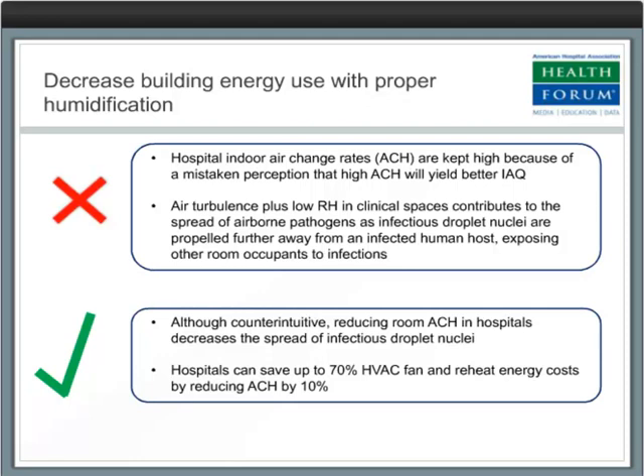There was a great paper that Travis English from Kaiser Permanente published at the ASHRAE meeting in 2015, describing a natural experiment in some California hospitals with natural ventilation. The findings were that you could reduce air change rates from 6 to 2 air changes, based on ASHRAE Standard 170, and get 70% savings in fan and reheat energy costs for a VAV system with an air side economizer.